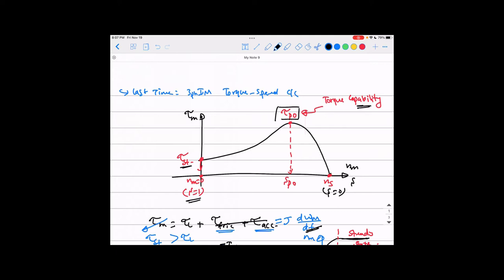You can calculate the starting torque using the equivalent circuit by setting slip equal to one, calculating the current, and then calculating the torque as usual. The rated torque of the machine is a little bit less than the pullout torque. The pullout torque does not equal the rated torque — the rated torque is what the machine is designed to work at continuously, and it is a little bit less than the pullout torque. The machine can produce slightly higher torque than rated, but only for a short amount of time, otherwise you are sacrificing the machine's windings.